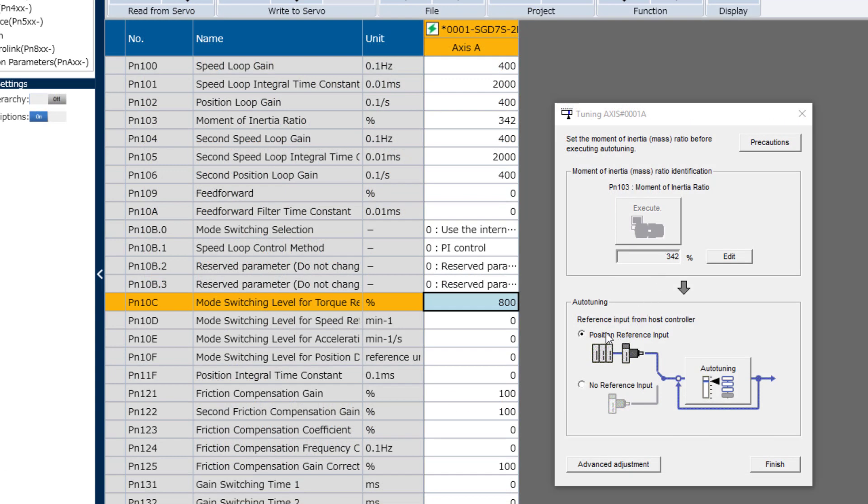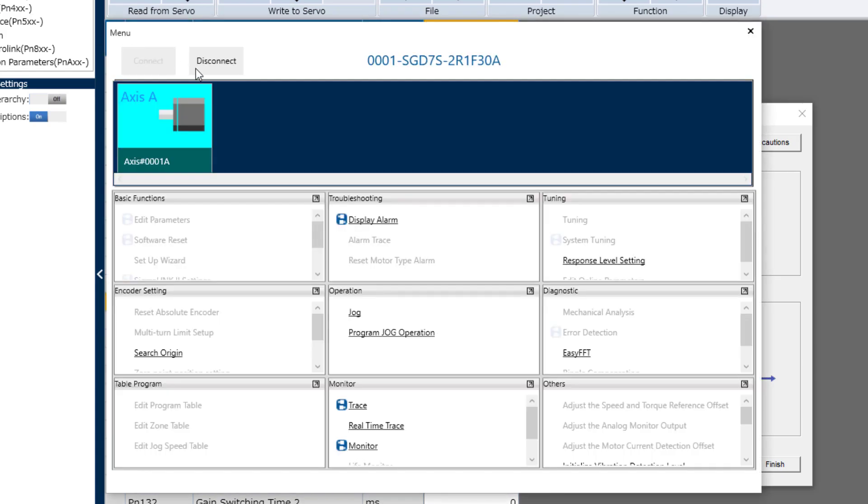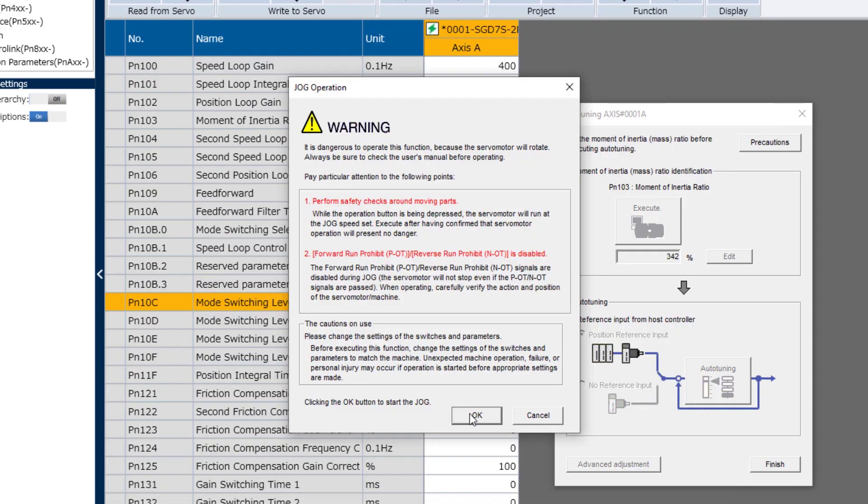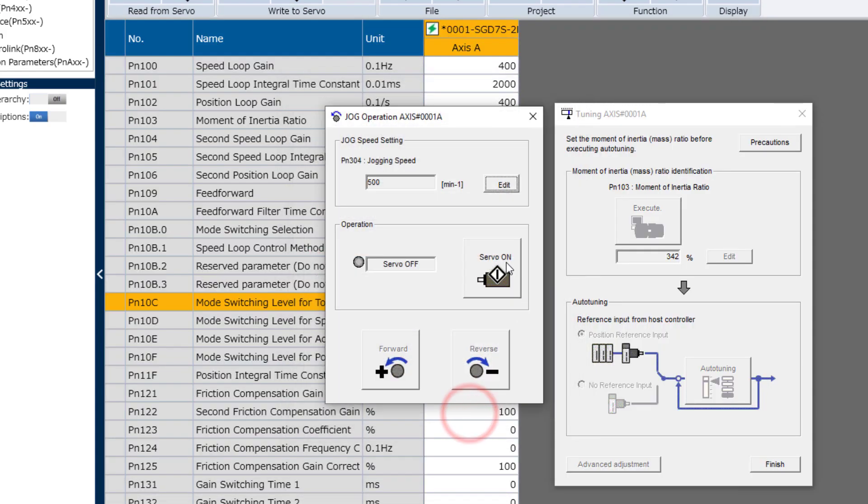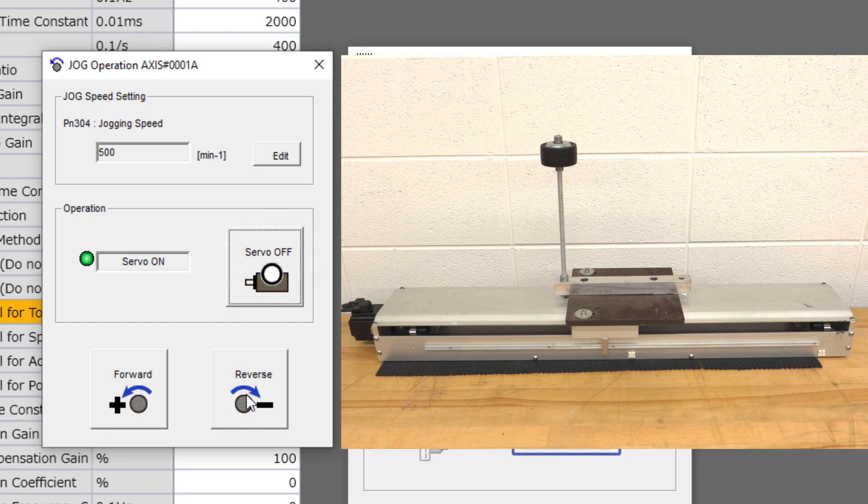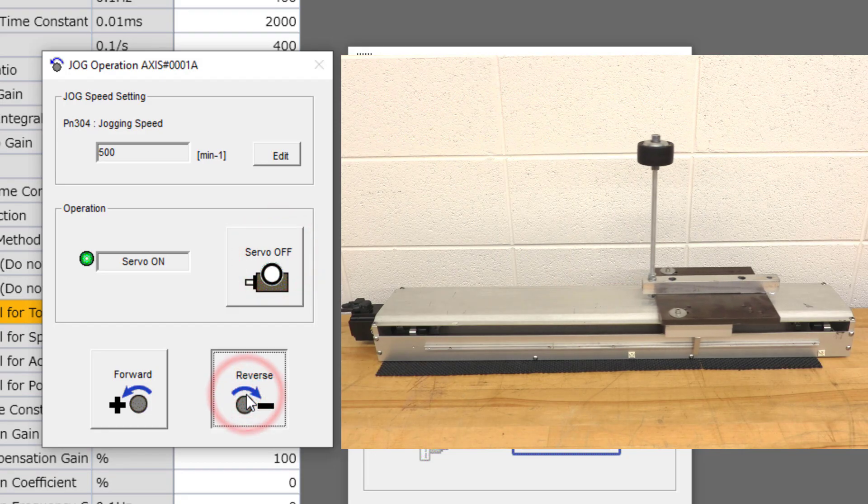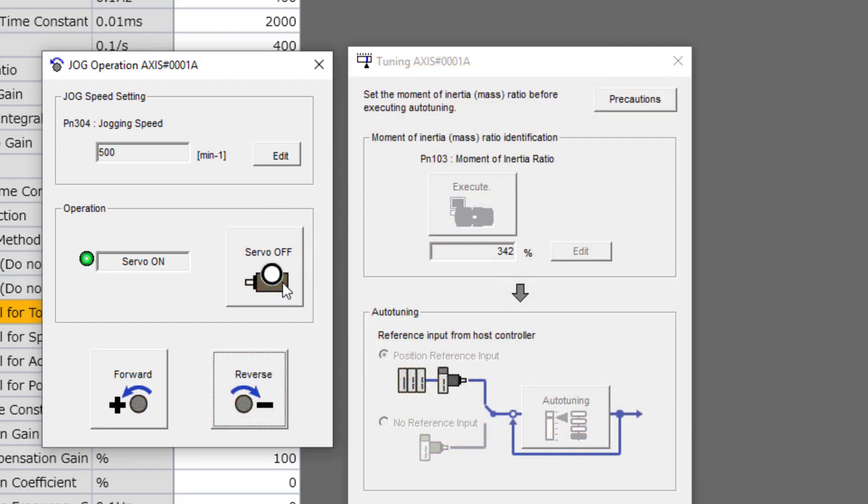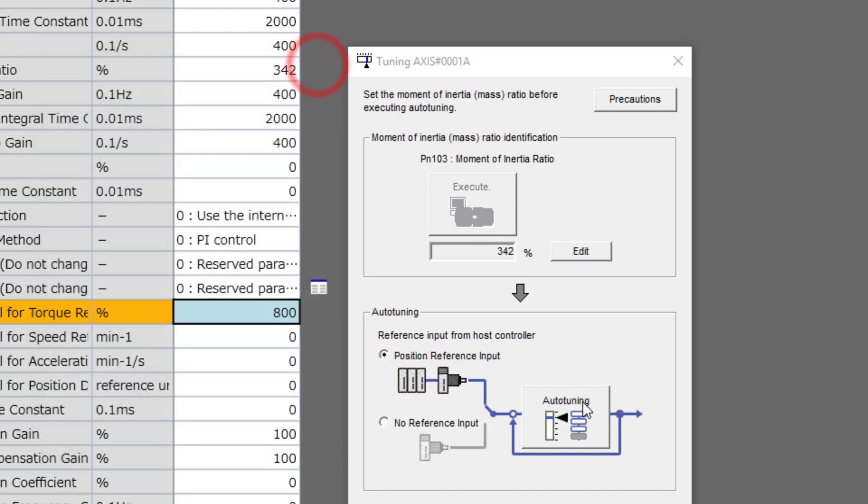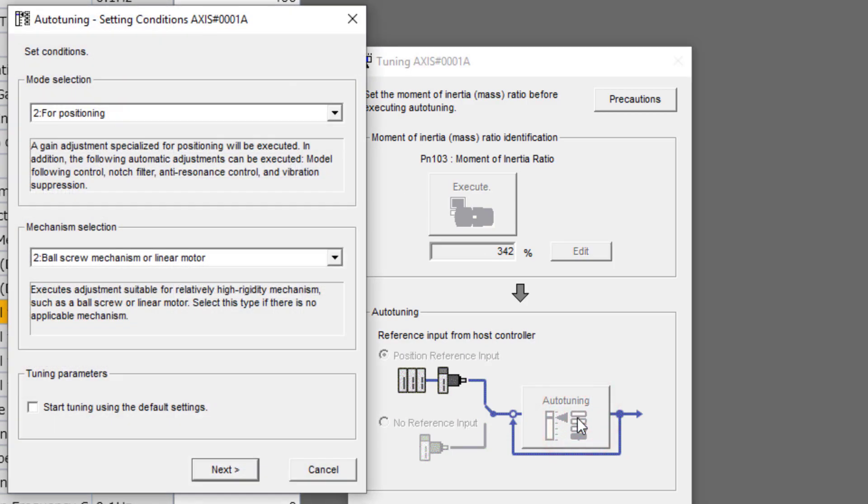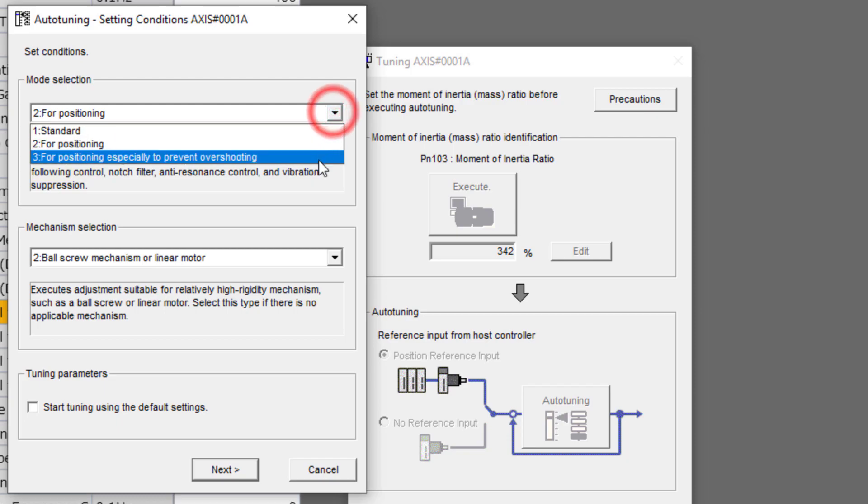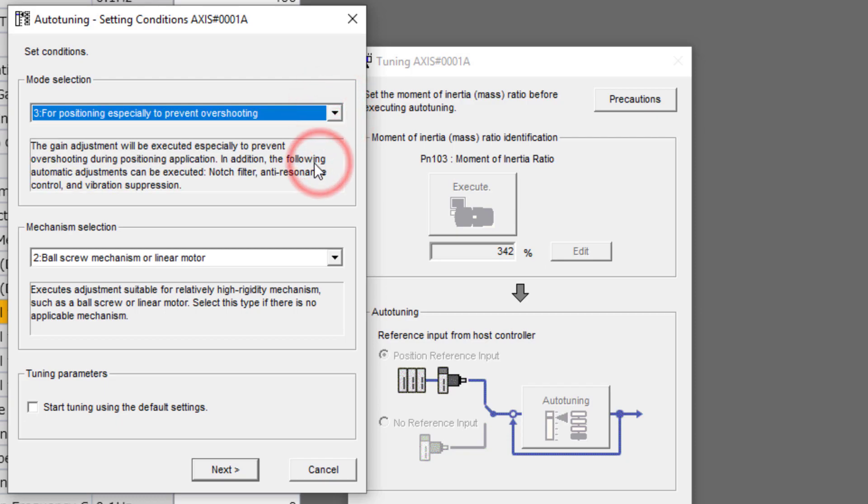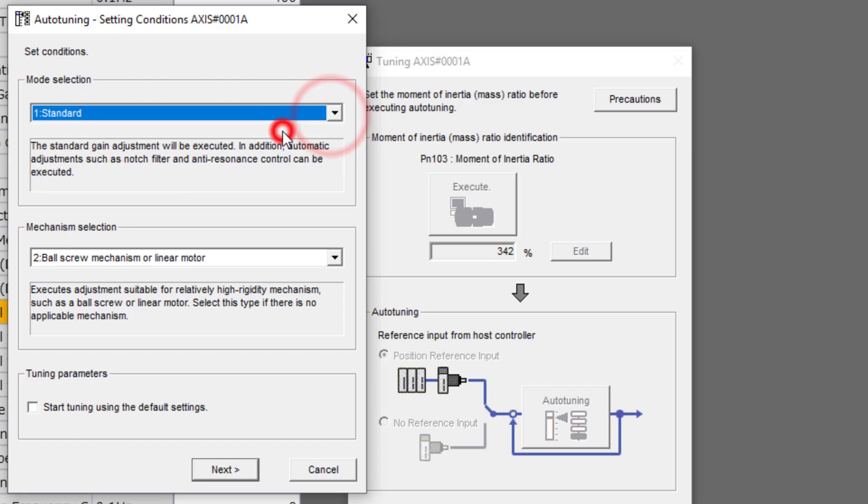Now we're ready for Auto-Tuning with position reference input from program jog. So I better jog that motor back to the starting position. Here in jog operation. In reverse. Okay, let's close this and now Auto-Tuning. Mode selection 2 mentions model following control. Mode selection 3 also uses model following control, even though it's not mentioned here. But mode 1 does not.